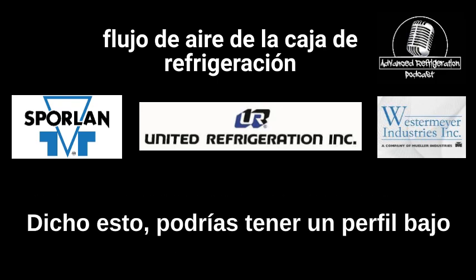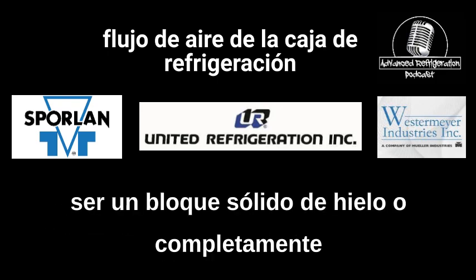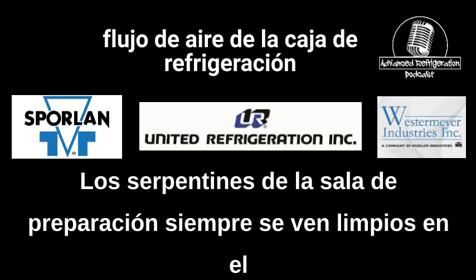With that being said, you could have low profile coils that look completely clean and not iced up, and the whole inside of the coil could be a solid block of ice or completely plugged with debris, like prep room coils. Prep room coils always look clean on the outside because they get hosed down nonstop, but the insides look like they cut a couple cats up in there.